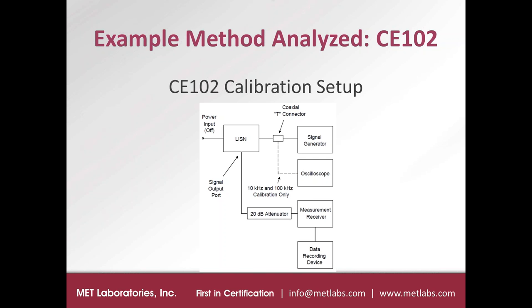This is the diagram of the CE-102 calibration setup from the standard, and this means the system level calibration, so not calibration of individual pieces of test equipment. Those are not covered under the standard. This is for the entire test system. You can see that a signal generator is used to send in a signal to the LISN. This port that it connects to the LISN is the port that would normally be where the EUT power comes out from the LISN and connects to the EUT. During the calibration, the power input is turned off and the signal generator is sent into that port so that we can measure that intentional signal on the actual signal output port that's connected to the measurement receiver.